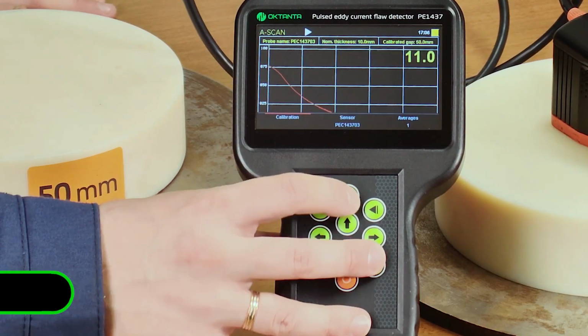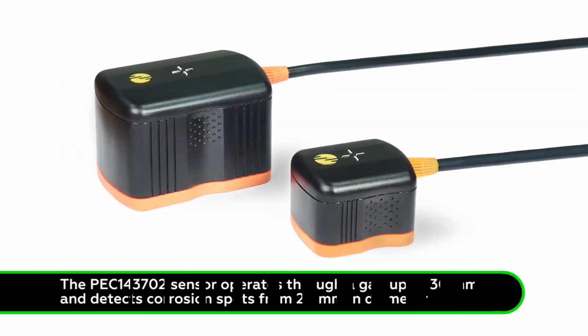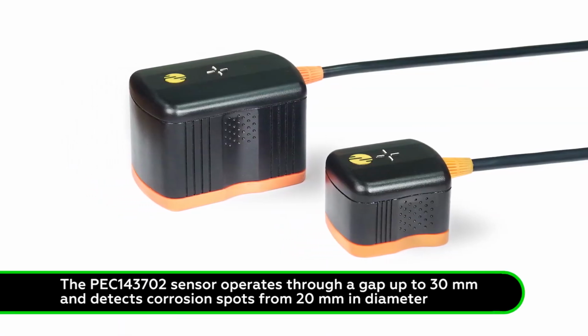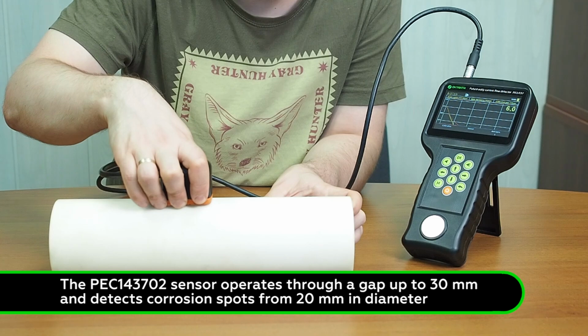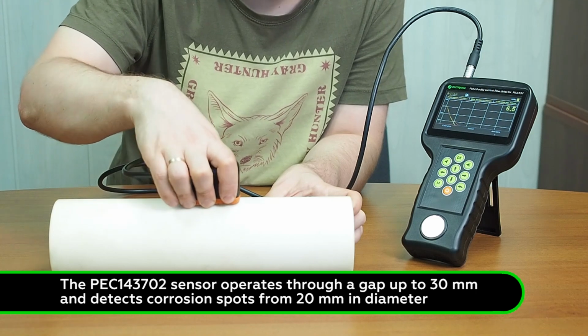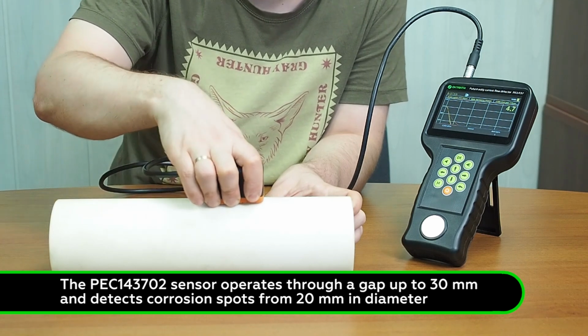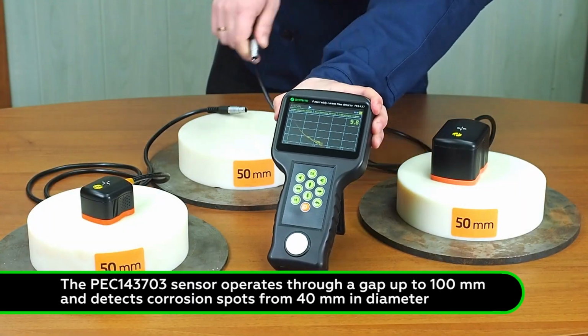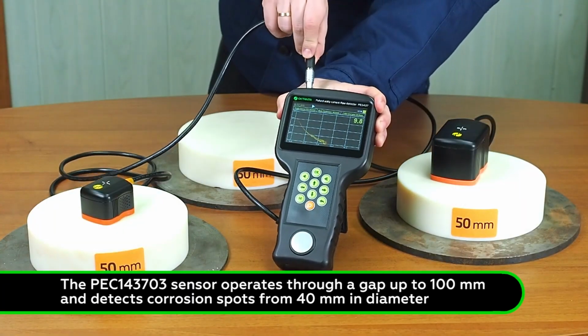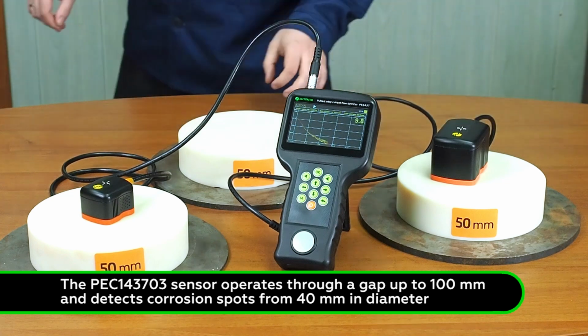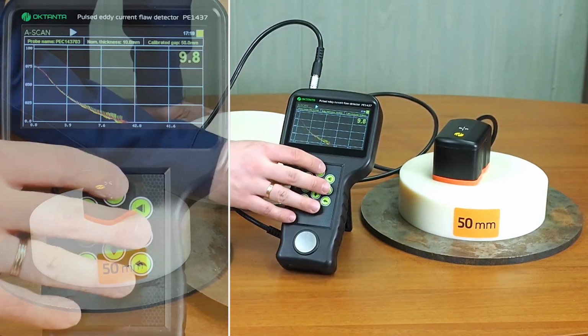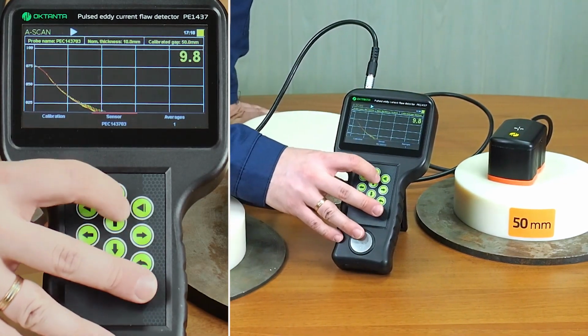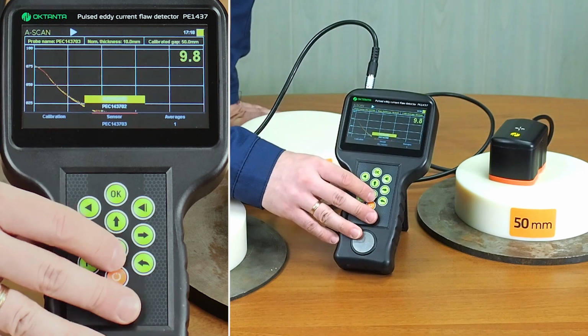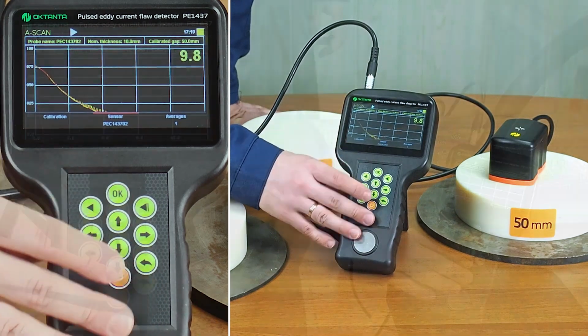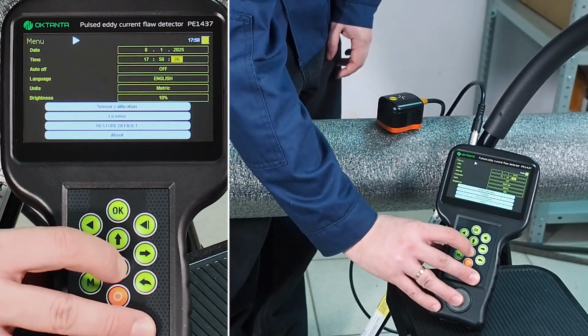The flaw detector can be connected to two sensor types. The small sensor operates through insulation up to 30 millimeters thick and detects corrosion spots from 20 millimeters in diameter. The big sensor operates through insulation up to 100 millimeters thick and detects corrosion spots from 40 millimeters in diameter. The sensor can be easily replaced. However, after replacement, you need to specify which sensor is connected to the device and to carry out a simple sensor calibration in the air.